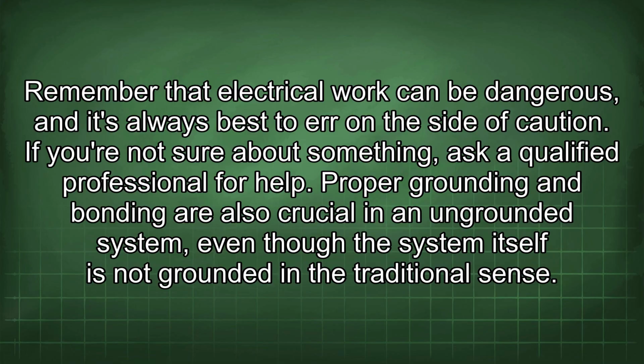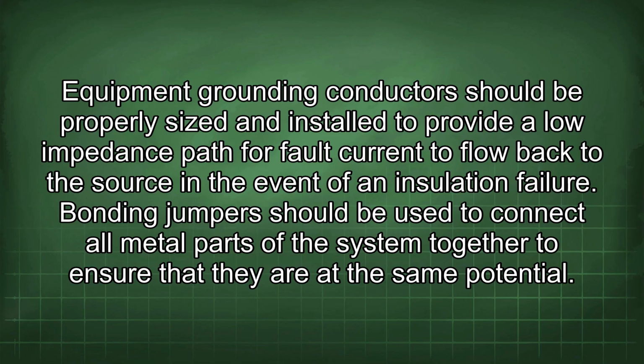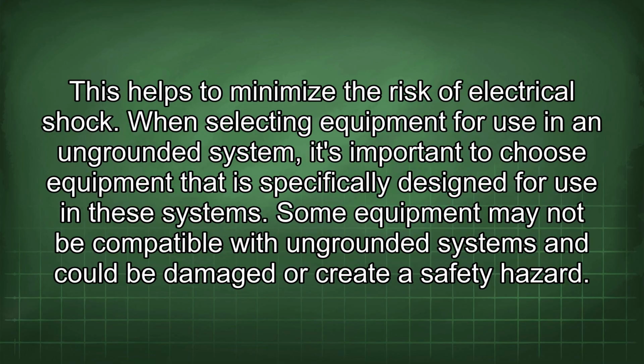Proper grounding and bonding are also crucial in an ungrounded system, even though the system itself is not grounded in the traditional sense. Equipment grounding conductors should be properly sized and installed to provide a low impedance path for fault current to flow back to the source in the event of an insulation failure. Bonding jumpers should be used to connect all metal parts of the system together to ensure that they are at the same potential. This helps to minimize the risk of electrical shock.